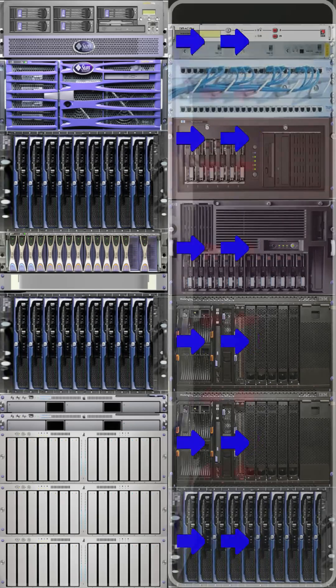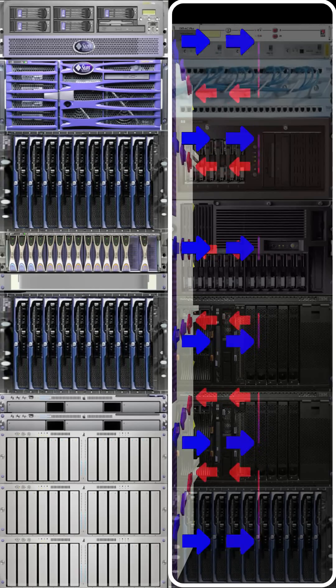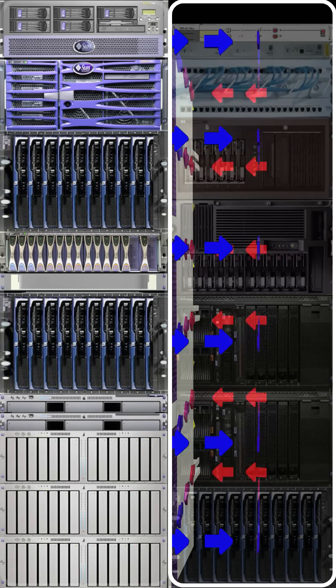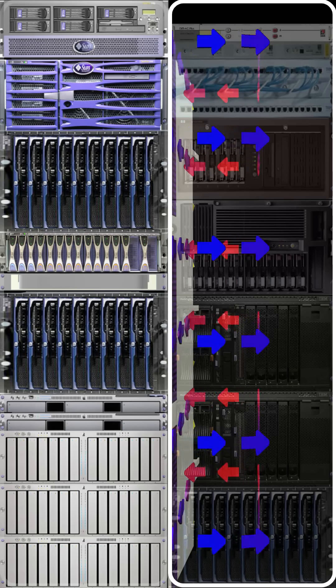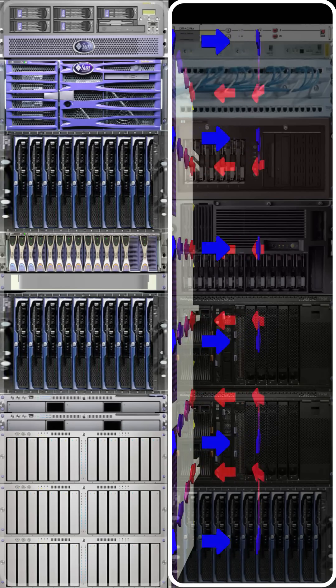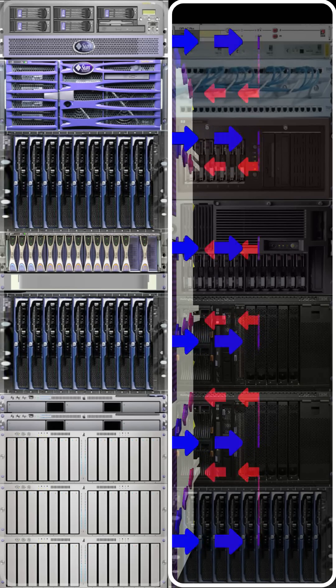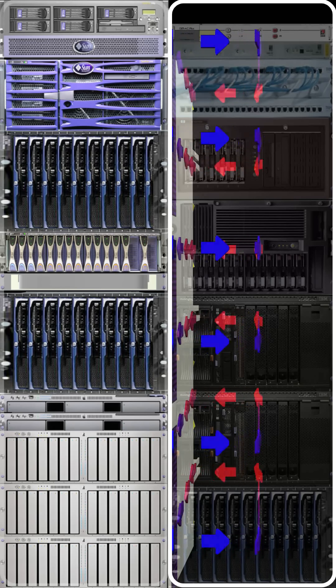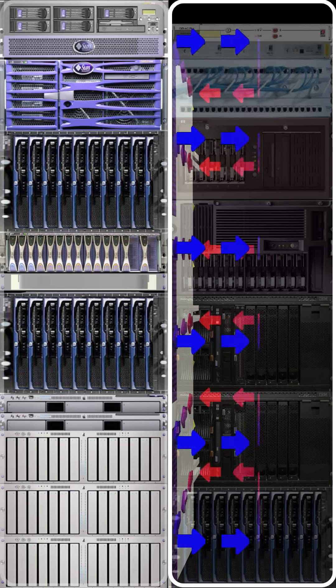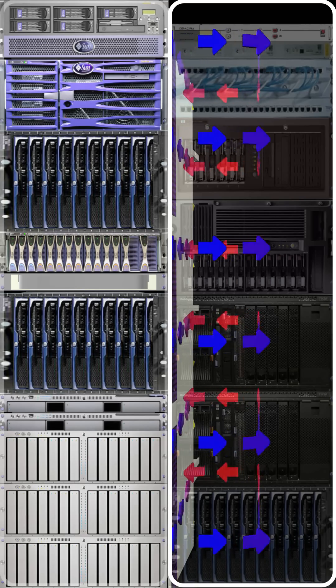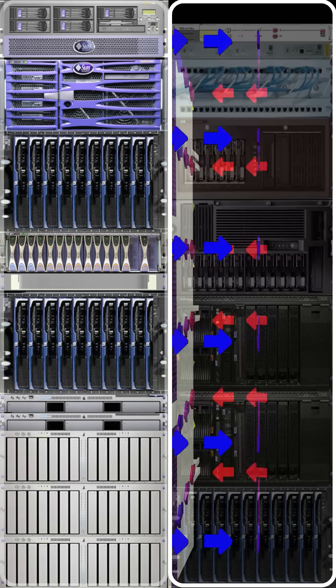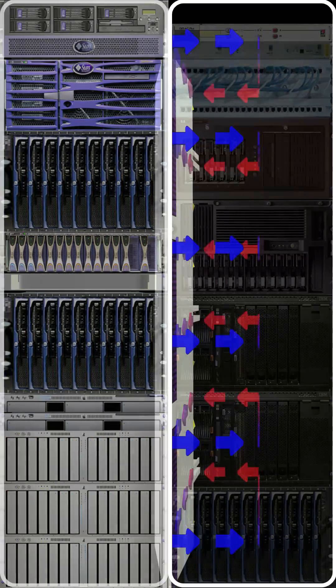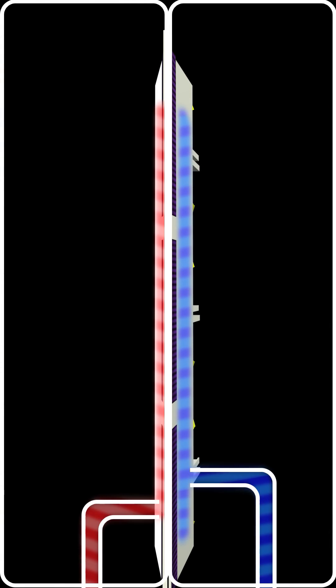It's been specifically designed to blow cool air across the whole height of the enclosure to ensure that there's no chance of having any hot spots developing. This is a closed-loop cooling system which focuses the cooling directly where it's required, physically separating the hot and cold air paths so they can never mix, which also significantly increases system efficiency.